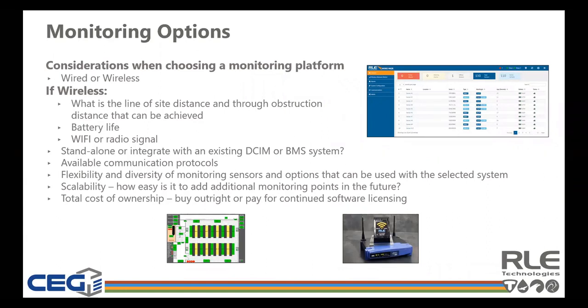Most monitoring solutions today use RF frequencies that don't interfere with anything else going on in the data center. There are frequencies allowed in the United States that are typically used by the manufacturers, and different frequencies in other parts of the world. But the RF doesn't interfere with anything. A lot of the transmissions from the sensors themselves are just temperature data, and most times that data is encrypted, so you can't even hack it and understand what you're looking at. And it's one way. It's one way out from the sensor and not back to the sensor.